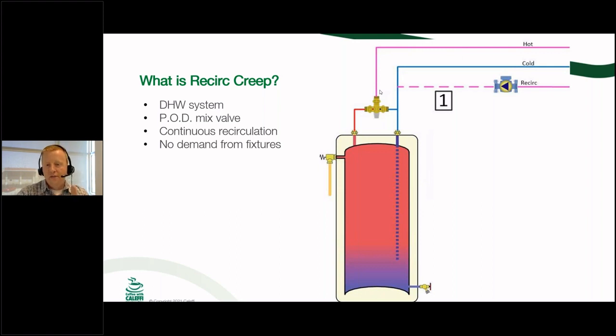So this diagram here is, again, very simple diagram. This is what we typically see out of your domestic hot water recirc tie-ins and everything like that back at the water heaters. But we've got a couple other ones here too, and I just want to address them real quick before we move on. The second one is if you have a tapping on your tank, and then it'll even be labeled right on there, recirculation tapping or recirculation connection, things like that. It'll be typically about midway up on the tank.